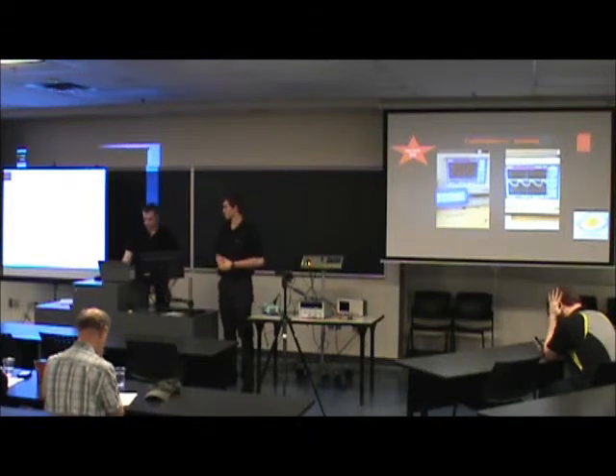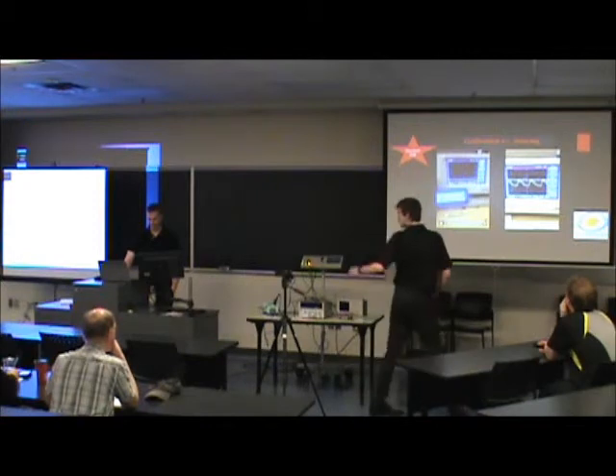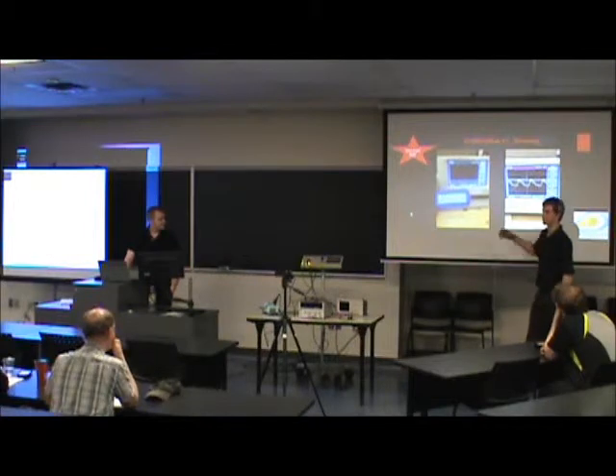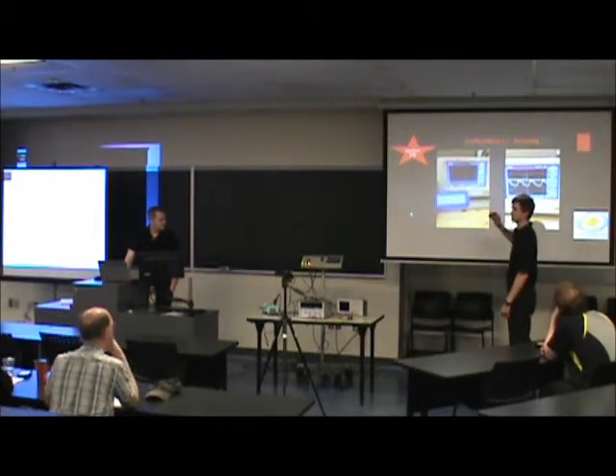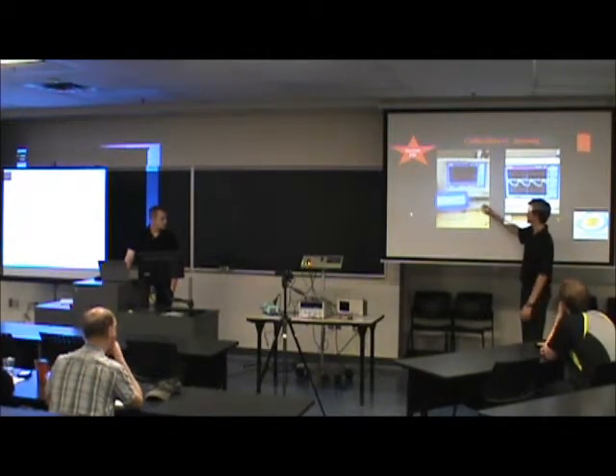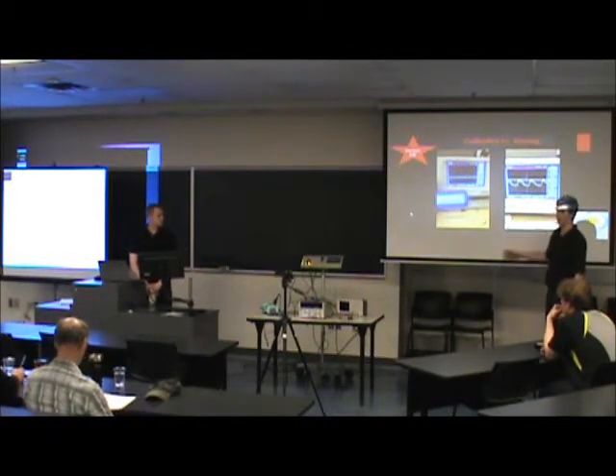So I'm going to be talking about section E in your marking scheme, which is the readout function of the screen. Just to change things up, we'll look over here a little bit, everyone kind of focusing on that side. On the left-hand side, we have our static level gain from 0, 40, 80, and 120. You can see that the output of the screen matches perfectly with 0, and then after a little peak, it comes back down to roughly 40 and 41, so it's still within plus or minus 3 millimeters of mercury for the calibration, as well as for 80, and perfectly at 120 millimeters of mercury.